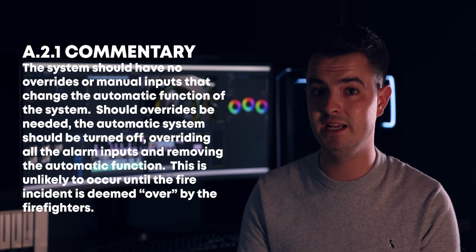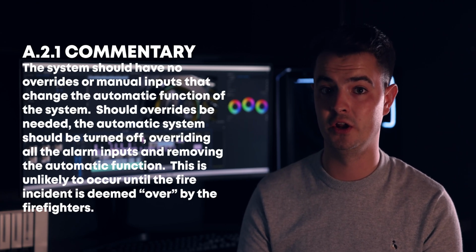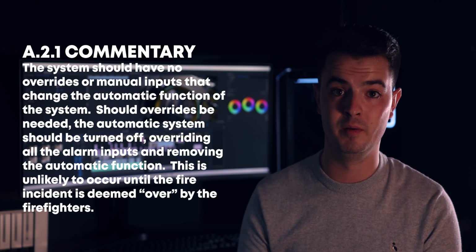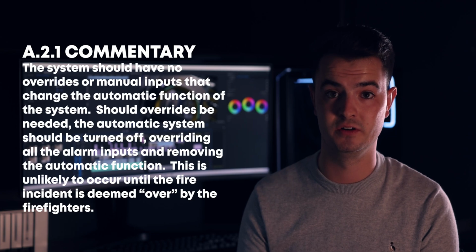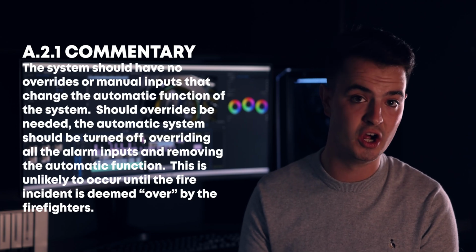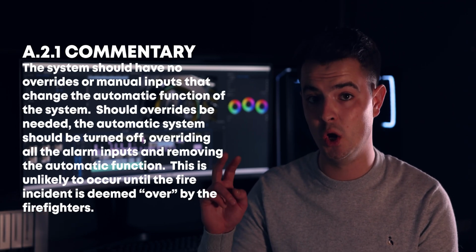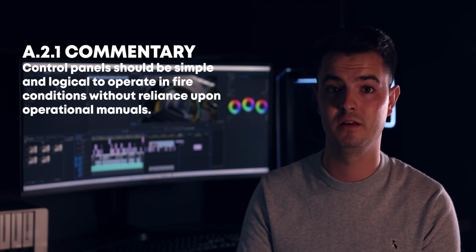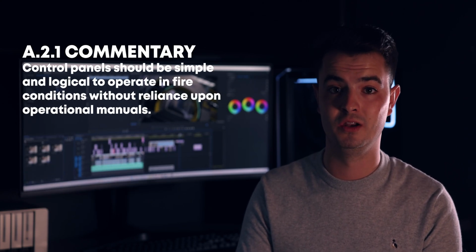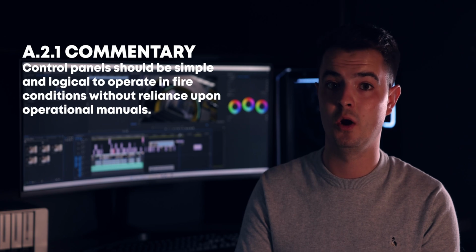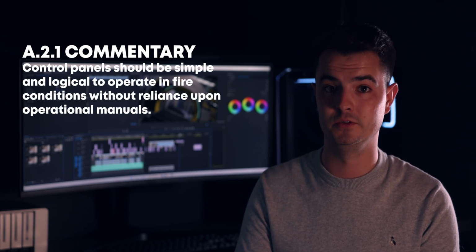Should overrides be needed, the automatic system should be turned off, overriding all the alarm inputs and removing the automatic function. This is unlikely to occur until the fire incident is deemed over by the firefighters. Control panels should be simple and logical to operate in fire conditions without reliance on operational manuals.